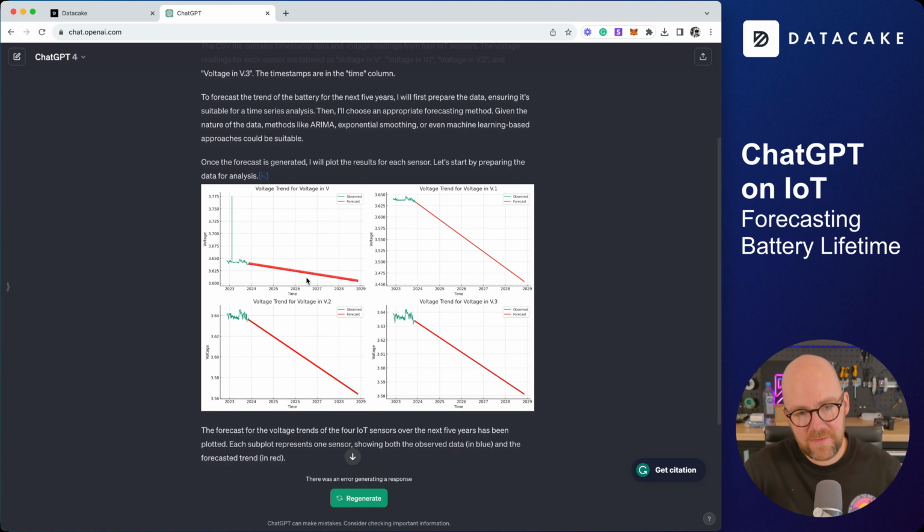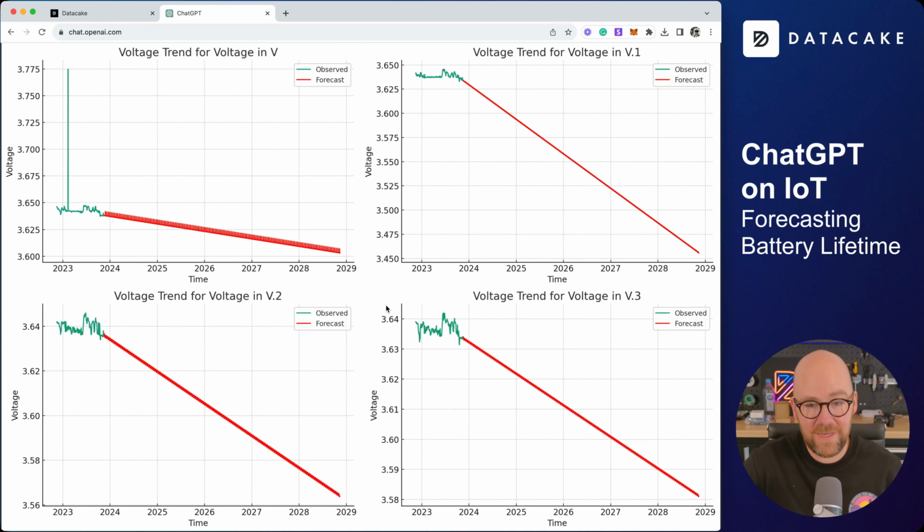You can see here the trends based on the sensor battery reading for 1 year. And still it's the case that in 2029, none of the sensors will be below the minimal voltage of 3.2 or 3.1 volts. This means that I need to create basically a new video in 5 years that will prove if this has been right or not.